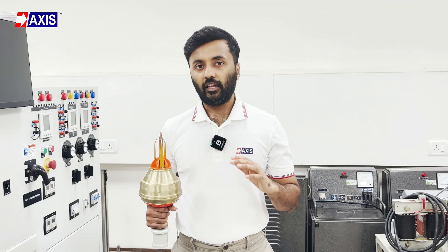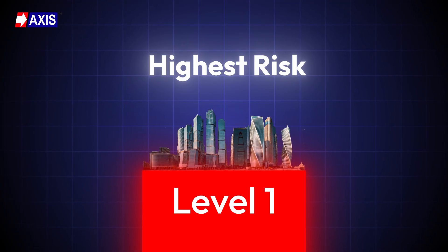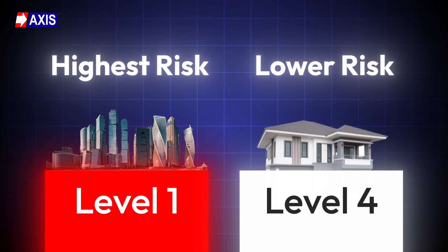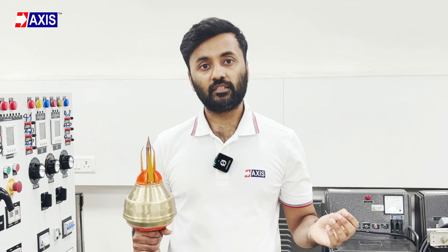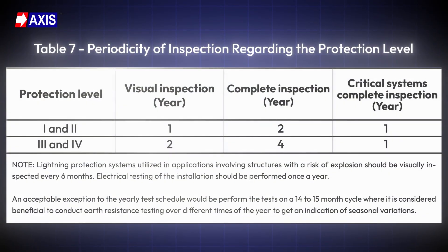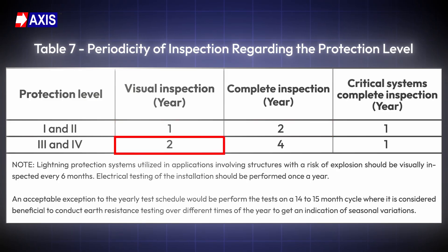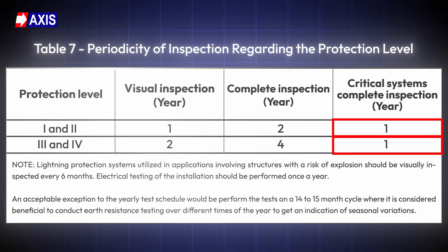Sixth, verification: lightning protection systems are classified by risk from level 1 to level 4. Level 1 is for the highest risk, like tall buildings or sensitive sites; level 4 is for low-risk areas like small structures. The lightning protection system must be verified after the ESE arrester is installed and checked at regular intervals as specified in table 7 of NFC 17-102. For protection levels 1 and 2, a visual check is needed every year and a full check every 2 years. For levels 3 and 4, the visual check is needed every 2 years and the full check every 4 years. Critical systems must be fully inspected every year, no matter the level.